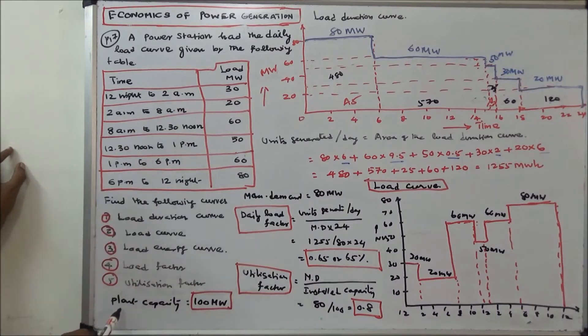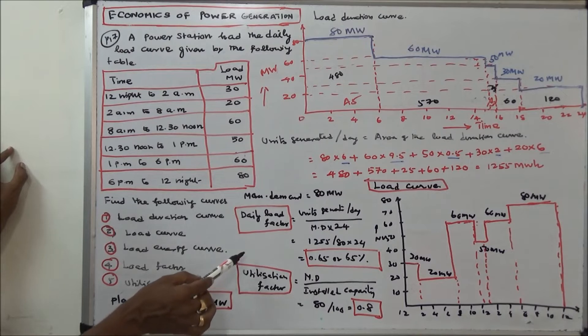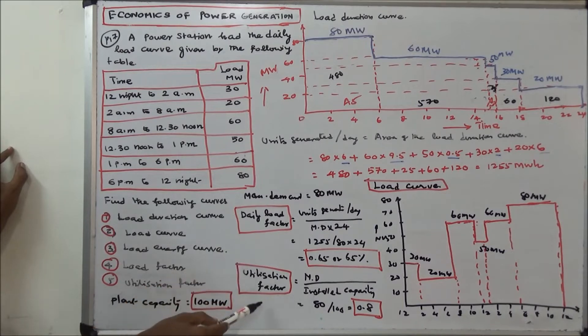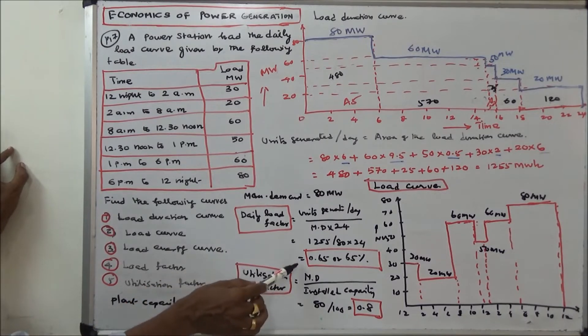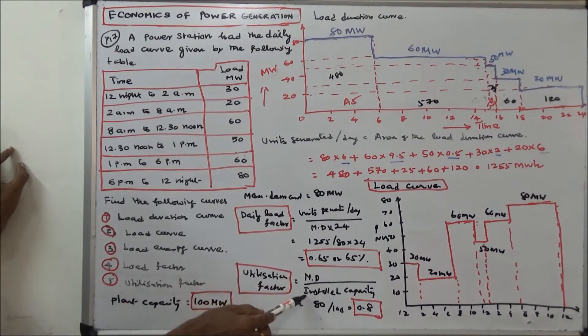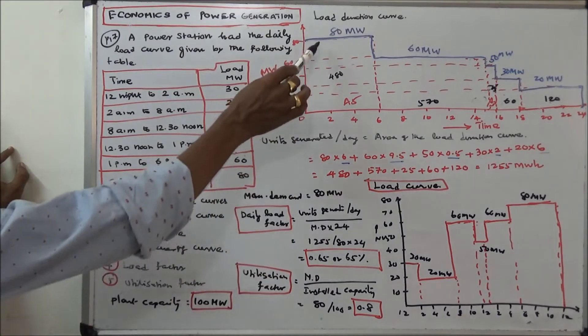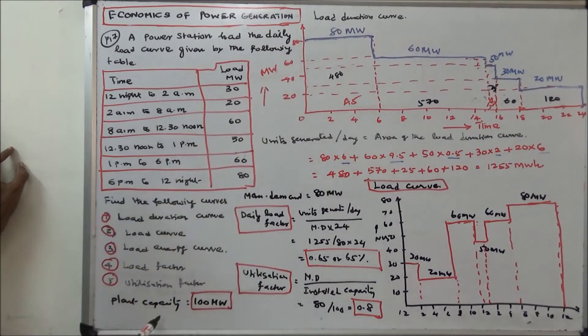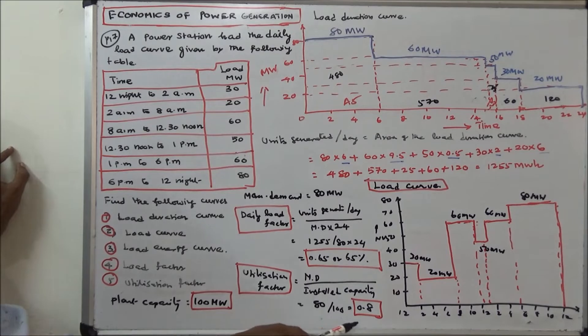The plant installed capacity is given as 100 megawatts, so we can easily calculate the utilization factor. Utilization factor equals maximum demand divided by installed capacity. Maximum demand is 80, installed capacity is 100, so 80 divided by 100 equals 0.8.